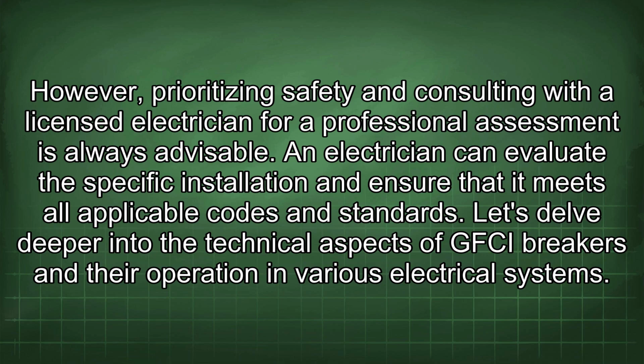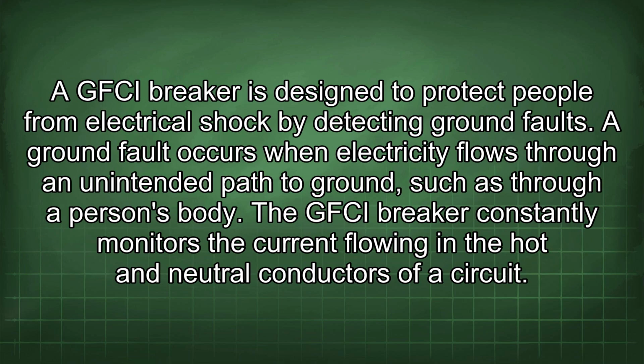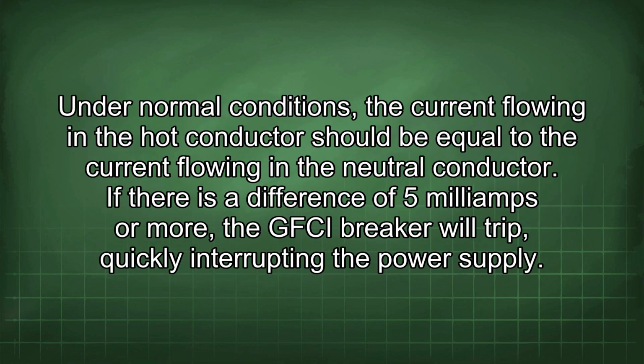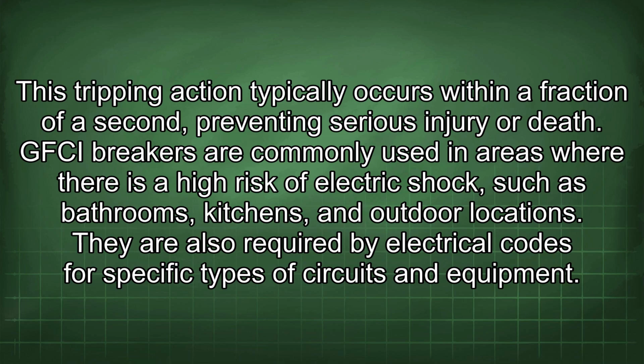Let's delve deeper into the technical aspects of GFCI breakers and their operation in various electrical systems. A GFCI breaker is designed to protect people from electrical shock by detecting ground faults. A ground fault occurs when electricity flows through an unintended path to ground, such as through a person's body. The GFCI breaker constantly monitors the current flowing in the hot and neutral conductors of a circuit. Under normal conditions, the current flowing in the hot conductor should be equal to the current flowing in the neutral conductor. If there is a difference of 5 mA or more, the GFCI breaker will trip quickly, interrupting the power supply. This tripping action typically occurs within a fraction of a second, preventing serious injury or death.